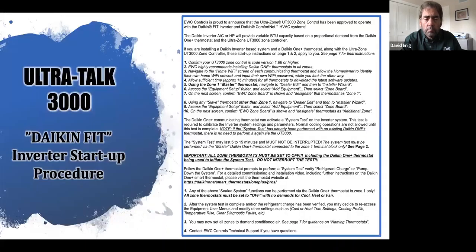We also have a procedure that's required. It's required the first time on startup that you have a Daikin One stat in zone 1 to do this inverter startup procedure. We give you an addendum in that installation manual that'll walk you through that startup procedure. Again, it has to be done once. It would not have to be done again on that unit. But the very first time it's commissioned, you need to go through this procedure. And it needs to be done from zone 1 with a Daikin One stat.